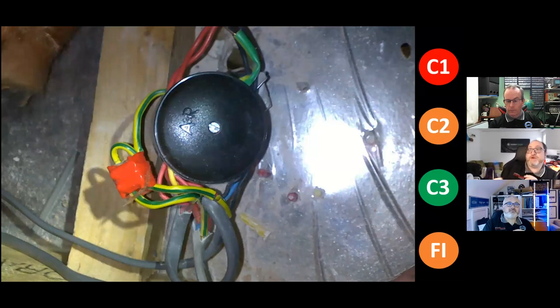Well, yeah. So these junction boxes have holes underneath them for fixing. The manufacturers specify they shall be fixed and the cables going into them shall be mechanically sound, clipped and all that. They shouldn't float. They shouldn't wave in the air. Indeed. So straight away, I could look at section 522, selection and erection of wiring systems, external influences, impact. You know, I could be crawling along the insulation. 526 is connections, and in there you'll find about the need for the cables to have mechanical and electrical continuity. And the fact that it could be covered in loft insulation, derating of the insulation.